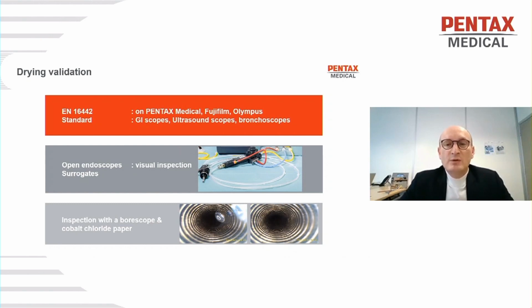And very often I get a remark that it's too simple to be true. So using open endoscopes where we put colored water and launch the process, we can demonstrate live how the system works and the efficiency of the drying. We also use inspection of the internal part of the channels. For undried channels, we can see some droplets here. And in the second picture, we can see that after the drying with Plasma Typhoon, there are no more droplets. We also use sensitive water paper, cobalt chloride, which allows us to check that the drying is done also on the external part and on the inlets of the endoscopes.